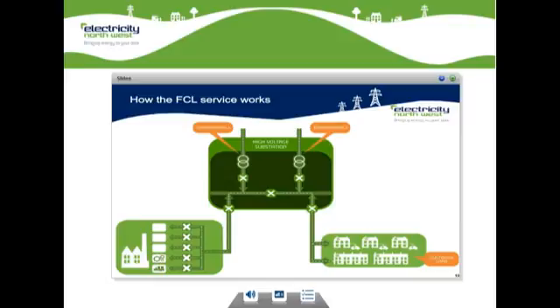So in the example where the fault current is higher than the equipment rating, how can we reduce it to a lower safe level before that breaker operates, so that we don't need to upgrade any of the equipment? One way of reducing the current is to disconnect the customer's motor and/or generator. Now this we would plan to happen instantly using the new technology deployed as part of Respond.